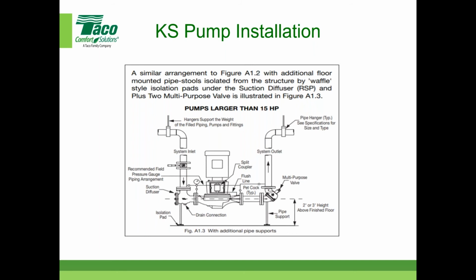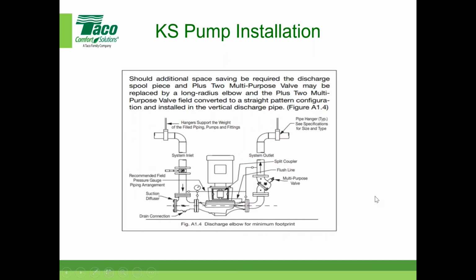Here's another potential way you could mount it, similar to the other one, but this is much closer to the floor. Some people might get a little worried by not having supports there. That isolation pad is a waffle type, meaning it has a waffled bottom that rubs on the floor. So it's not bolted to the floor, it's really just a pipe support. You can see in this case nothing is holding this down like a base-mounted pump where you actually bolt it to the floor. So something to consider as you think about stuff like that.